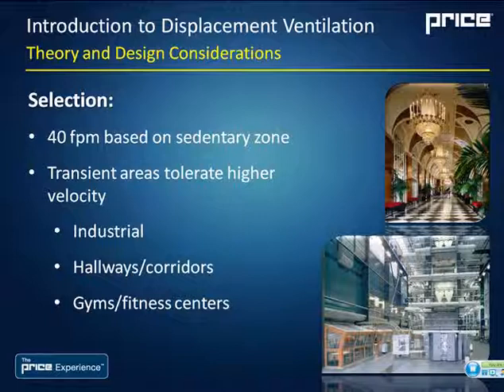hallways or corridors or industrial spaces, they might appreciate a little bit higher velocity, and it's also going to save you on diffuser sizing and get you a little bit more cooling efficiency out of a single diffuser. So you can actually up the velocities. In some cases for industrial diffusers, we see face velocities of 100 to 150 feet per minute.